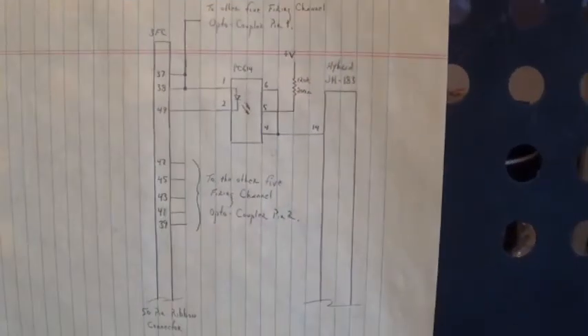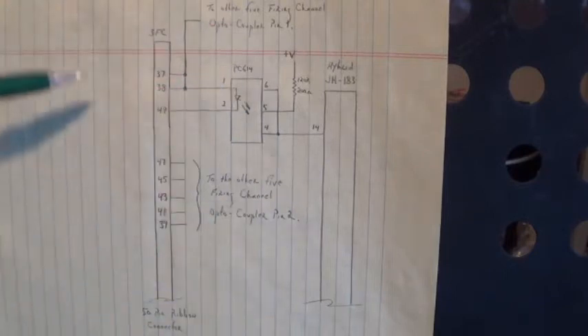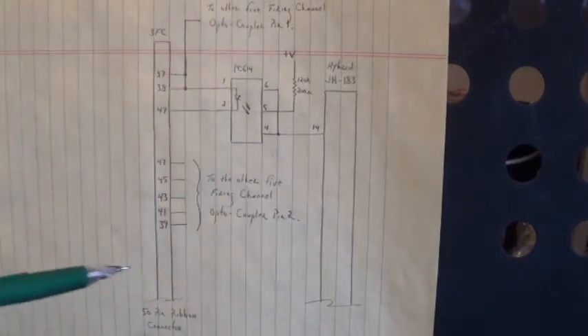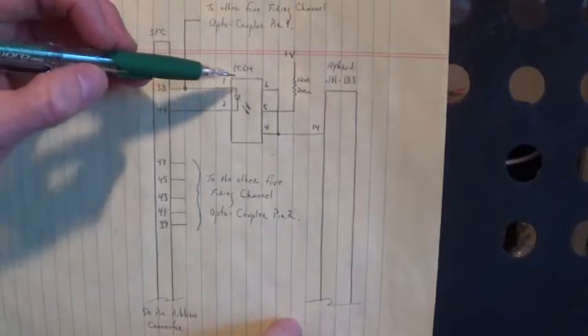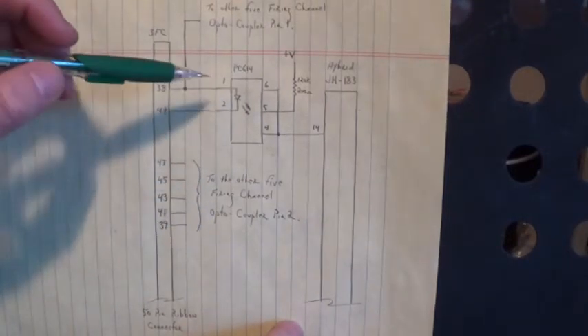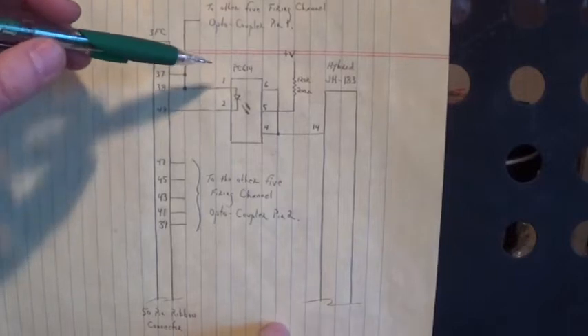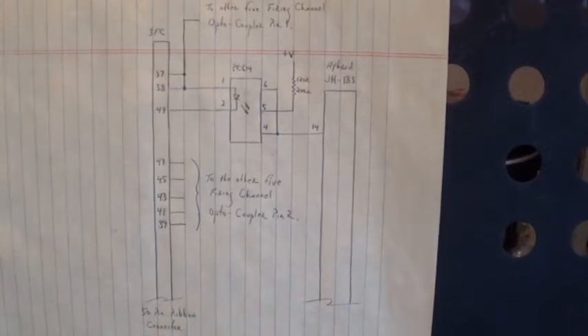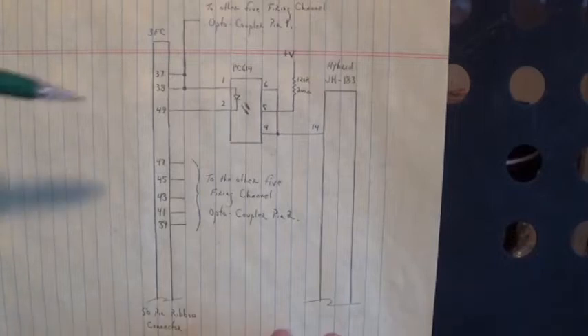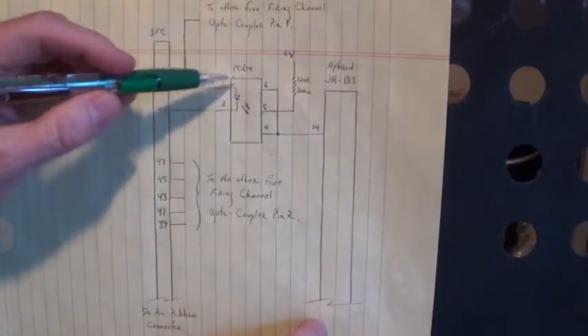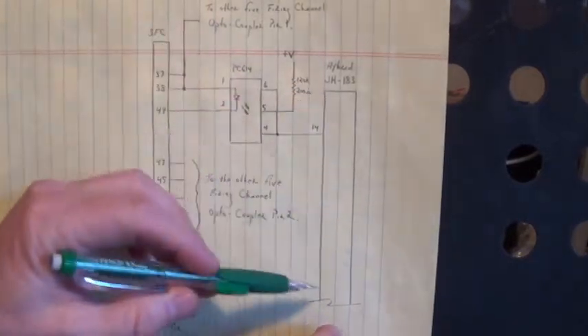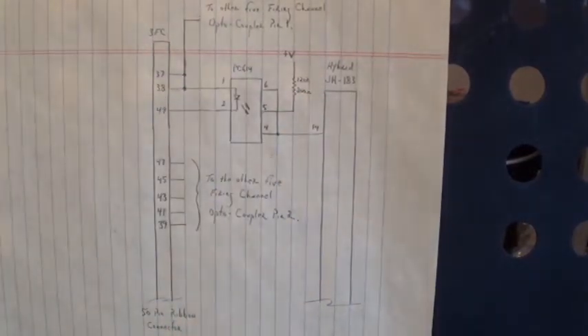In order to test the firing channels on that firing board, we have to understand the circuit. Each of the 6 firing channels that run that motor, that drive into the base of those transistor power modules, has an optocoupler. So we have 6 optocouplers. We have 6 hybrid modules.